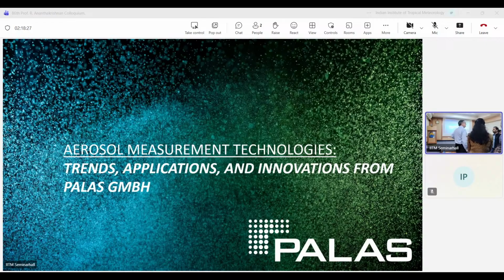Like laser light, we have alignment. For me, there is no concern. No, because we align not the laser, we align the amplification. Yeah? And this is not necessary. We first go by the photomultiplier increase of the amplification voltage and nothing else. It has a longer lifetime than a laser. So this LED, the power is more or less similar, but they are easier to handle.